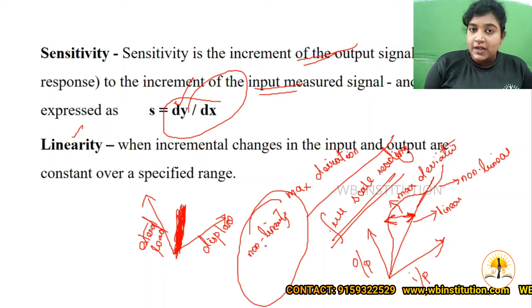So here the maximum deviation is the deviation in this area. The value you obtain for this area is said to be the maximum deviation. This maximum deviation is divided by the full scale reading. Already you will be knowing. From this you can calculate the non-linearity of your particular measuring instrument. Hope you are clear with what exactly linearity is.